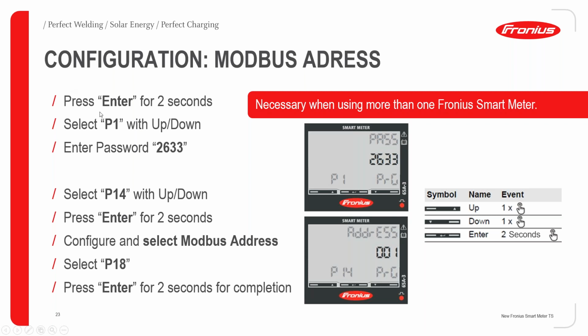So when you press enter for 2 seconds, then you will be in the programming page. Then you have to select P1 with the up and down button. As soon as you go to P1, it will ask for the password. You have to enter the password 2633. It's the same. And then after entering this, you will be allowed to move down in the P program buttons. Then you will go to P14. Then you press enter for 2 seconds, then you will enter into the menu. So always press enter for 2 seconds to enter into any menu or to save any settings.